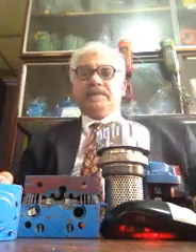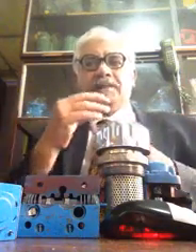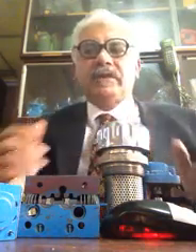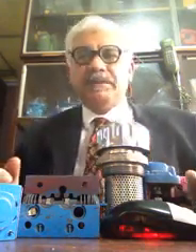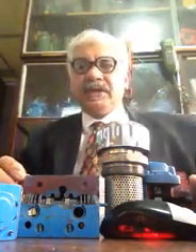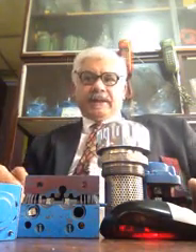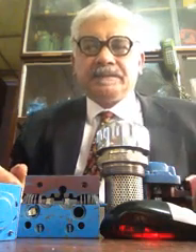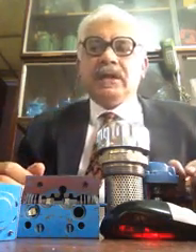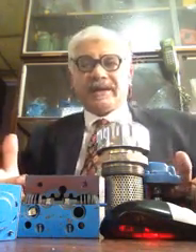And what is frequency? The number of times an action occurs in a unit of time is called frequency. Frequency is the basis of all sound. A pump or motor's basic frequency equals its speed in revolutions per second multiplied by the number of pumping chambers. Now, front connected: a condition where piping connections are on normally exposed surfaces of hydraulic components is called front connected.